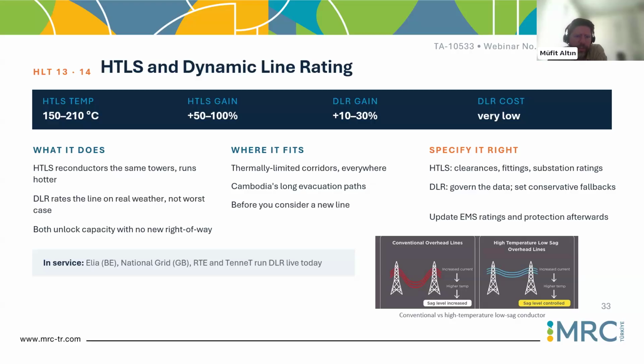I don't know about the HTLS implementation, but when you would like to increase the temperature and get more power, with the low sag issue, you can install these elements, and with the weather conditions you can, of course, couple or correlate them. I know one case or a couple of cases for wind farms. When the wind is high, you are producing more power from a wind farm. So for the lines connected to that, even if they are the classical, conventional ACSR lines, together with the wind effect, you can gain some margin to put the power. But this is a bit critical, of course.